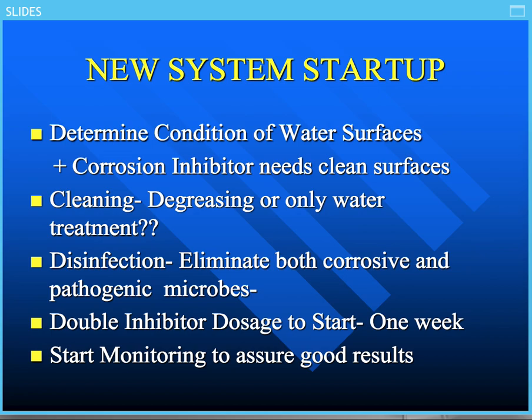What else is there? Disinfection. A new system should always be disinfected to eliminate two types of microorganisms. One is those that cause corrosion on mild steel and copper alloys and other alloys, and pathogenic ones, particularly Legionella. But any type of biological control, because in the process of construction of a new cooling tower water system, there are sometimes dead legs, sometimes there's water that's been left in there for a period of time that could be contaminated. And then when it starts up with a regular treatment program, you could have a lot of biological contamination, and that could be the source of corrosion and even pathogenic organisms.